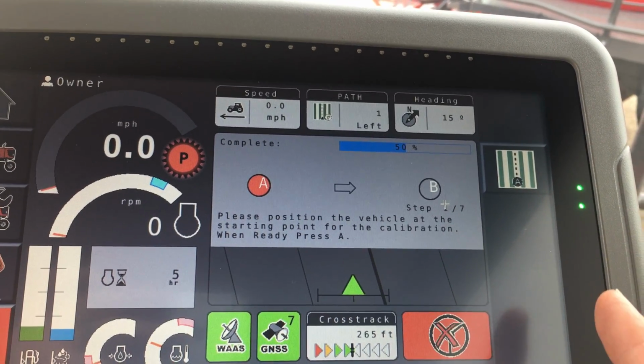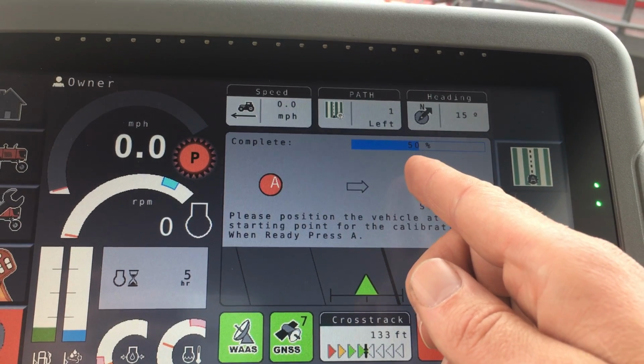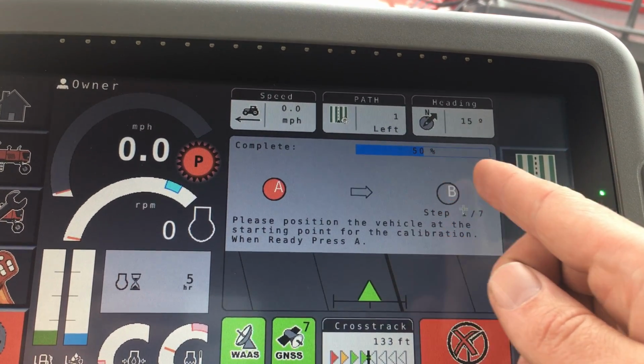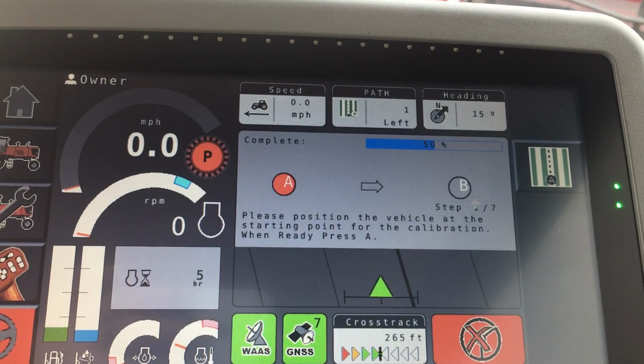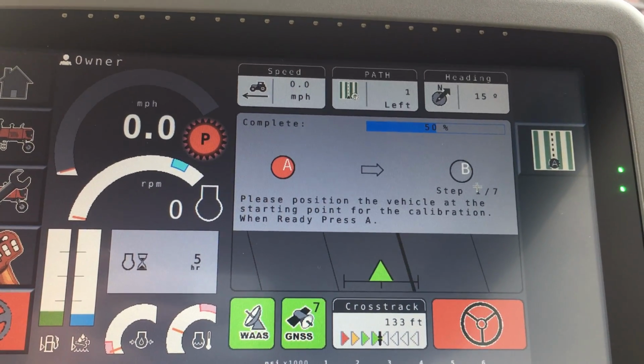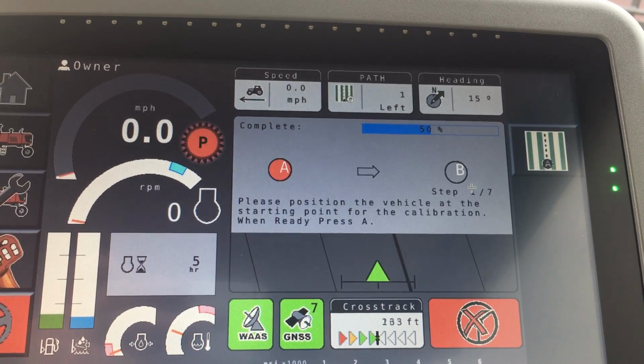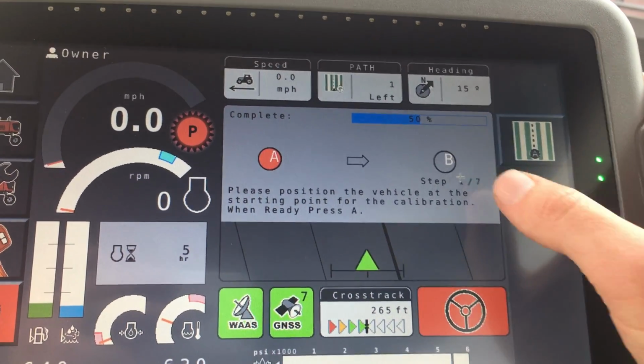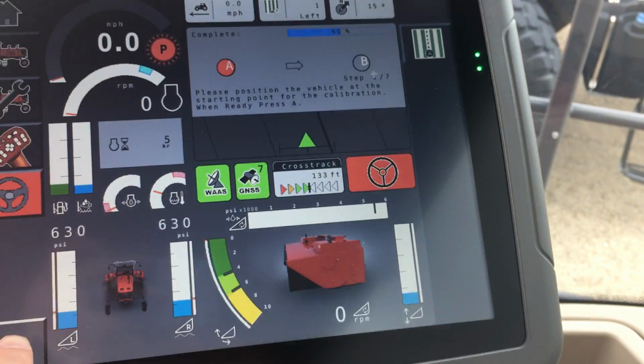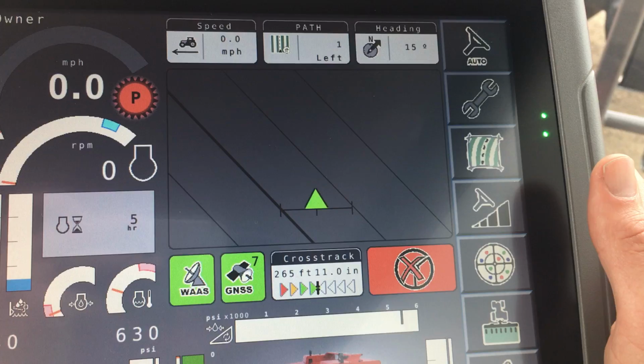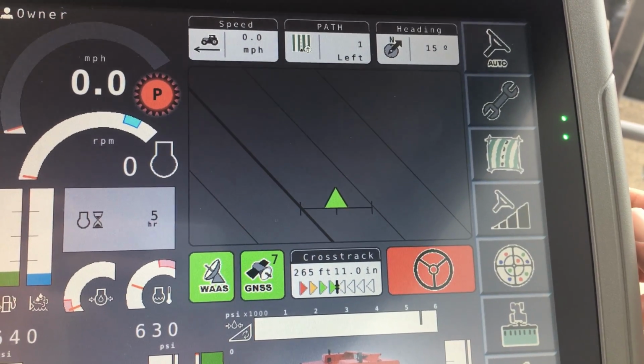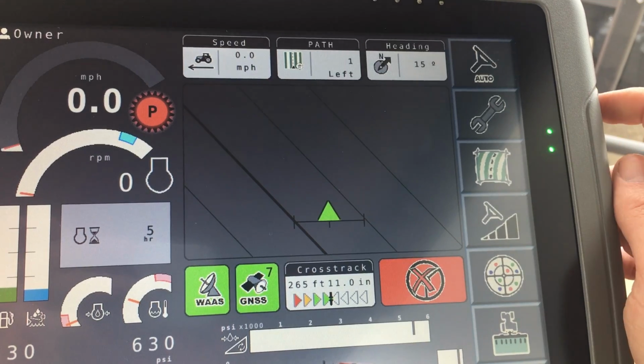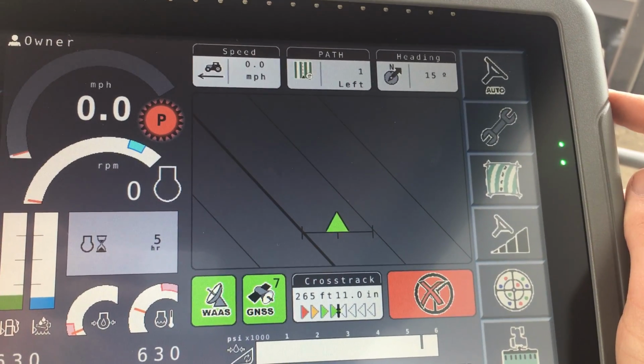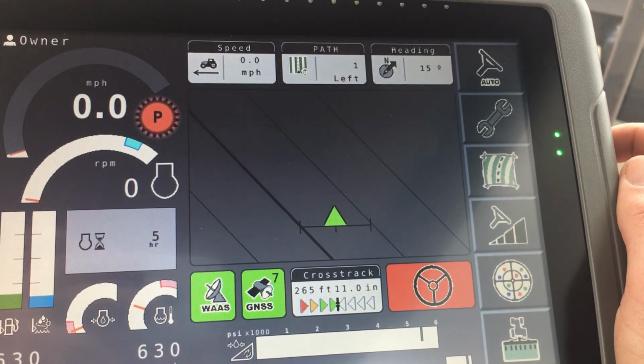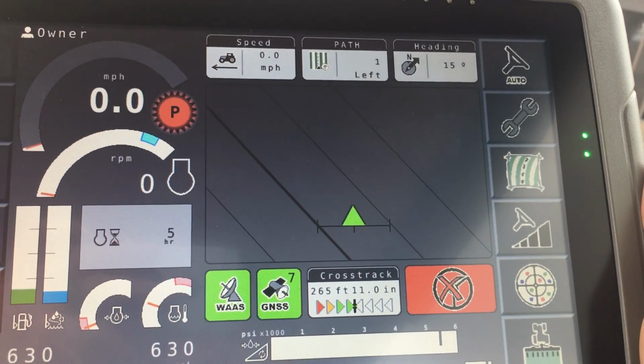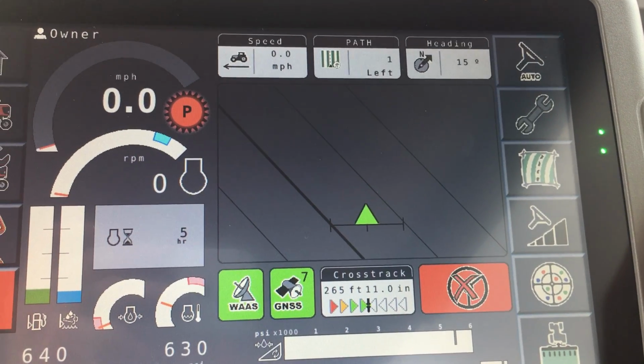And so when you drive down, it ends up getting to 50% when you get down, turn around, and start coming back, and if it picks up from 50% and goes to 100%, great. If it doesn't work, you might have to do it again. You may have been going too fast, bad signal, a number of things that could be going wrong, but eventually that will say successful. Again, I don't want to mess it up, so I'm going to go ahead and leave it there. But calibrations, at least those two, it's not a big deal to go ahead and do those every year, just to make sure. But again, guys go years without doing it, and it is okay, but that can be a source of inaccuracy, so it's good to do that.